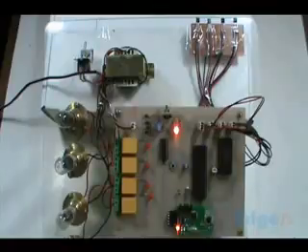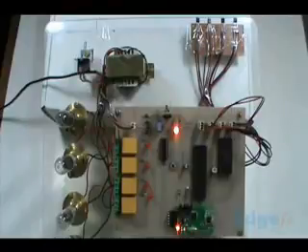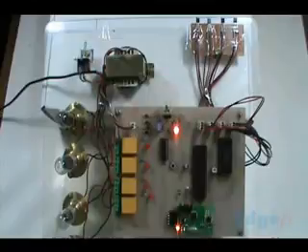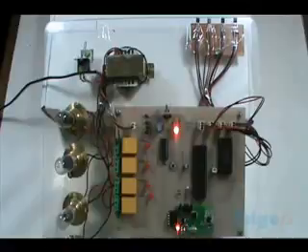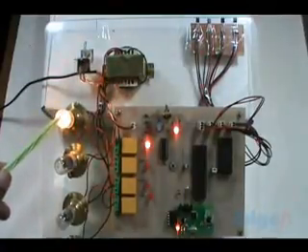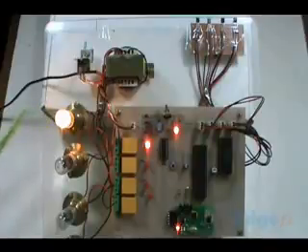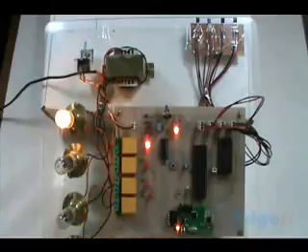Once the temperature is set, none of the heaters are on, because the set temperature is different from the field temperature. This is the field temperature, coming from the field. Now let's change the set temperature and see. When the set temperature is changed, we find that this heater is switched on. After the heater is switched on, the temperature goes up, and accordingly the others will also get switched on or switched off depending on the screen. We will see that from the screen.